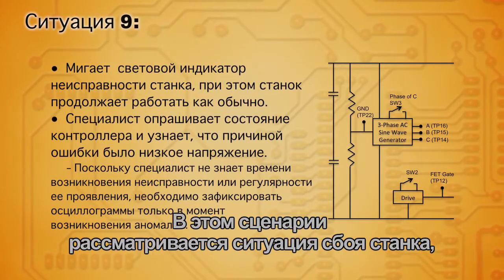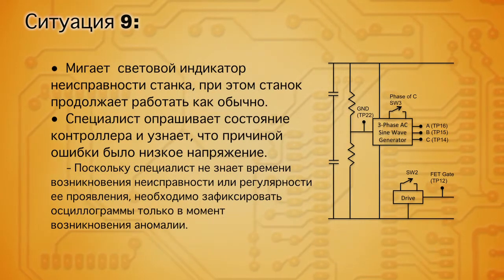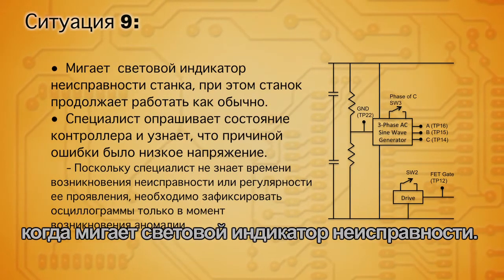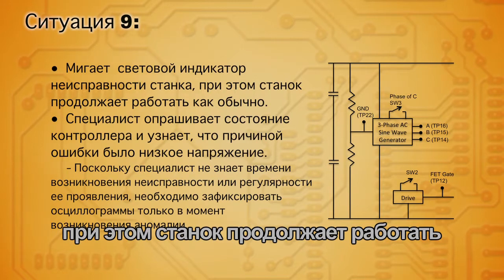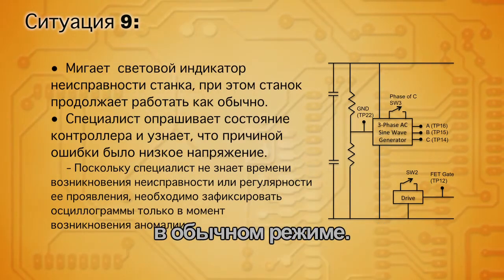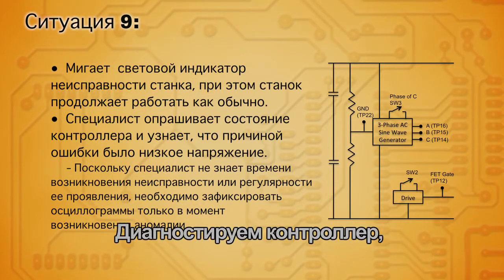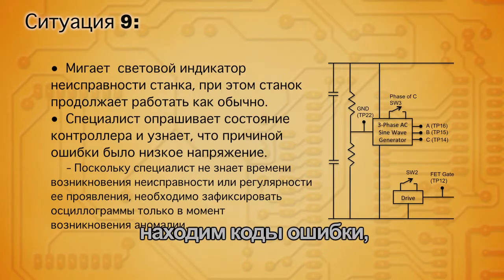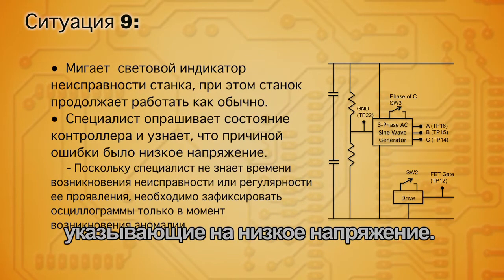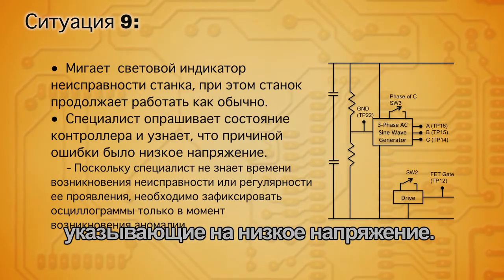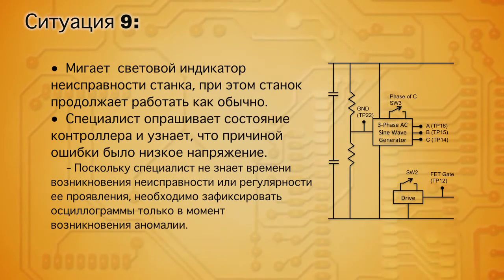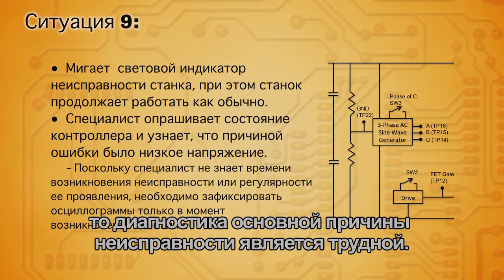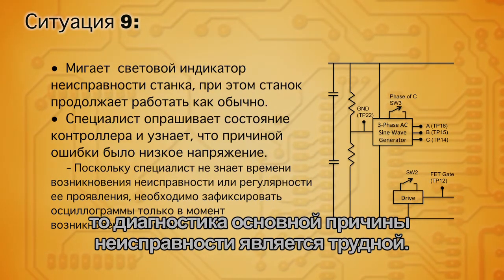Here we have a scenario where you have a critical machine with a fault LED flashing, but the machine is continuing to operate normally. Diagnosing the controller, you find the error codes indicate there has been a low voltage condition. Since you don't know when the fault occurred or how often it's happened, it's difficult to diagnose the root of the problem. This is one of the most frustrating circumstances for an engineer — these random events that cause an error but allow for otherwise normal operation.